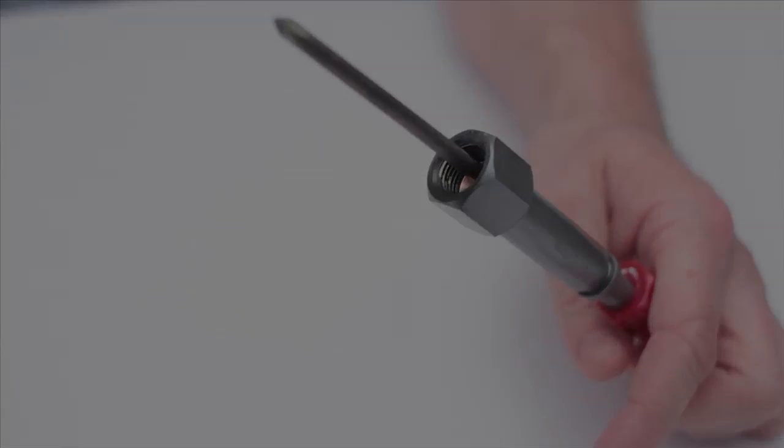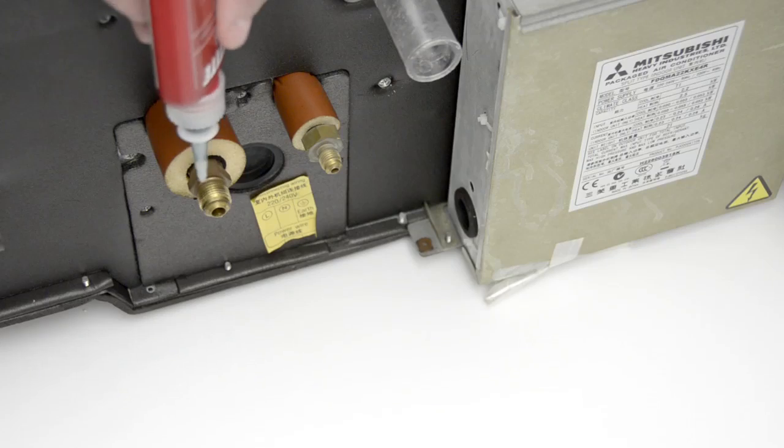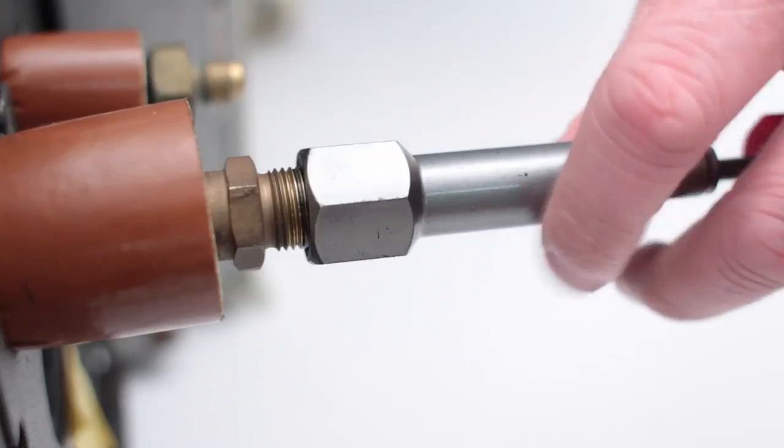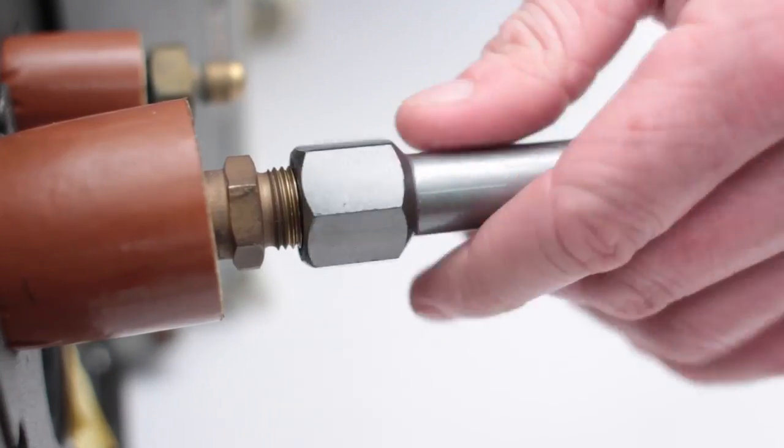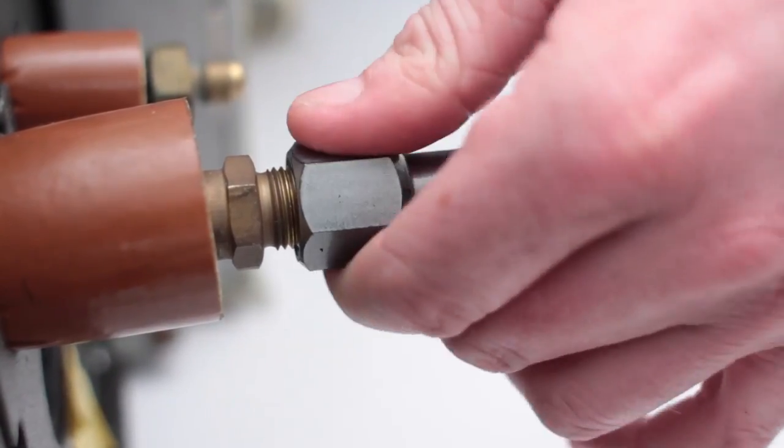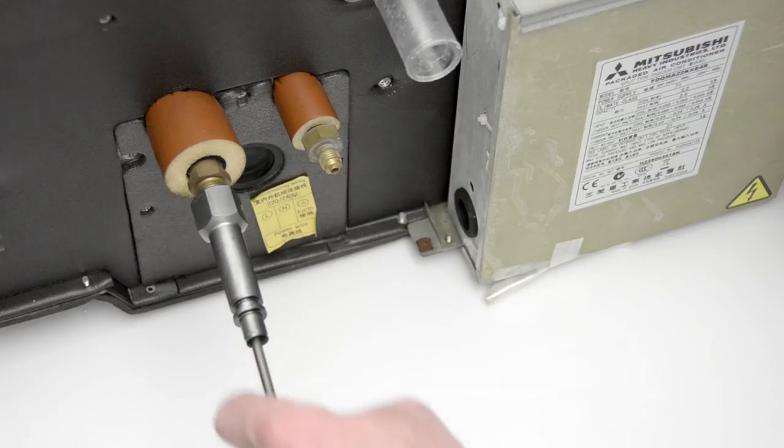Prepare the fan coil connection by applying lock preparation fluid. Insert the screwdriver tip into the fan coil connection and screw the body onto the fan coil connection until finger tight. Remove the screwdriver.